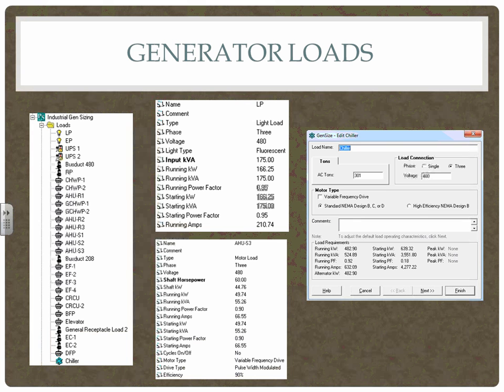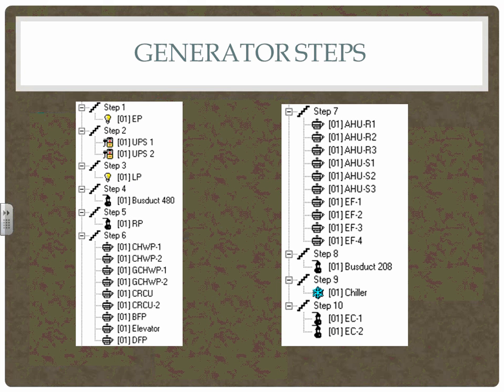This is through Cummins PowerSuite. We had to build all the loads and enter in all the information. So like here's the lighting panel. We had one of the air handling units. And then we entered in each step. So first, once we lost power and the generators picked up, the first would be the emergency panel. And then we had the UPSs, lighting panels, bus ducts, and then mechanical panels, just to make sure that we had what was necessary coming up first.